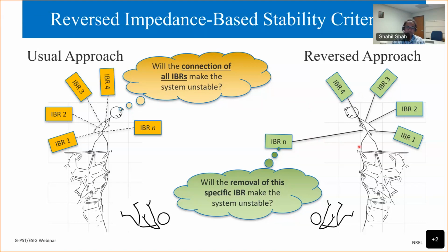Earlier, the fundamental premise was that the IBR is stable without the grid, or without the practical grid, and the grid is stable without the IBR. What happens when we connect them? That approach is not scalable. Here, the approach is that the IBR and grid are stable together. The IBR is also stable when it is connected to a hypothetical ideal grid. We want to ask the question, what will happen to the grid if I remove this IBR?